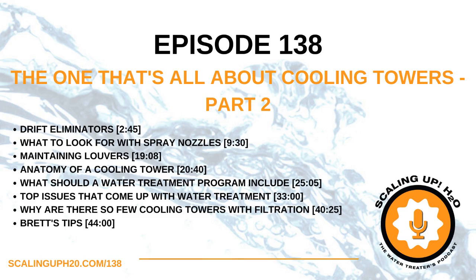And then the second one is I see a lot of softeners being in play as a treatment, softening the makeup water to a cooling tower or a closed circuit cooler. That's great because a lot of the times, hardness in the Midwest is high. And so you want to knock it down to reduce the scaling potential. The issue with soft water is when you're making up 100% softened water to units that have galvanized steel, that is a corrosion issue for that zinc. So we'll see companies that are softening the makeup water and then they have a galvanized coil in that closed circuit cooler, and they're seeing the zinc stripping off of that coil quicker than if they were just using the regular city or well water.